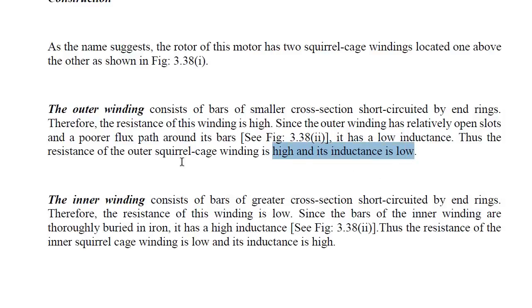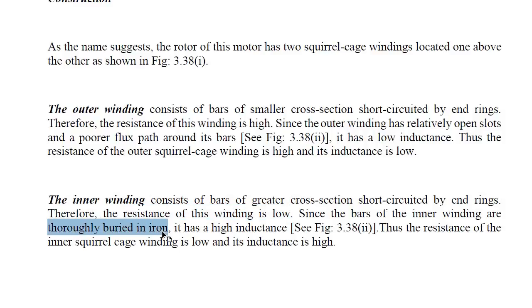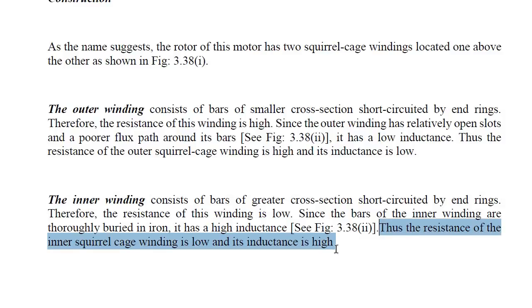The inner winding consists of bars of greater cross-section, short circuited by end rings. Greater cross-section means lower winding resistance, since R = ρl/A and R is inversely proportional to the area. Since the bars of the inner winding are thoroughly buried in the iron, it has high inductance. Thus, the inner cage winding has low resistance and high inductance. This is the basic construction of the double cage squirrel cage rotor.